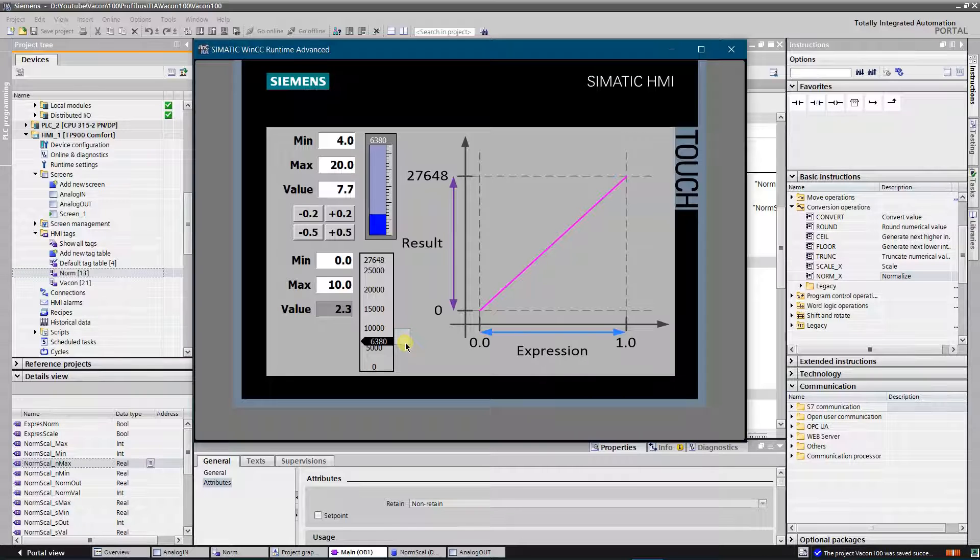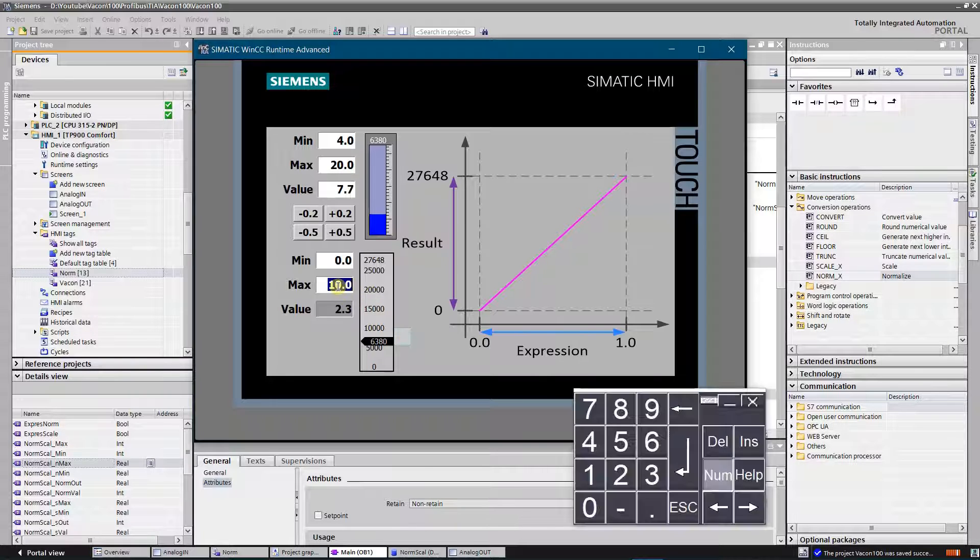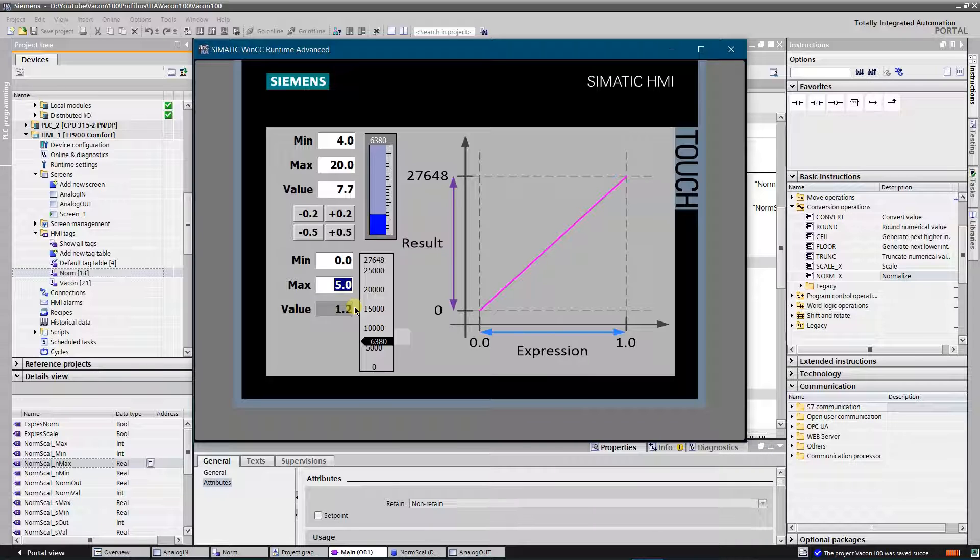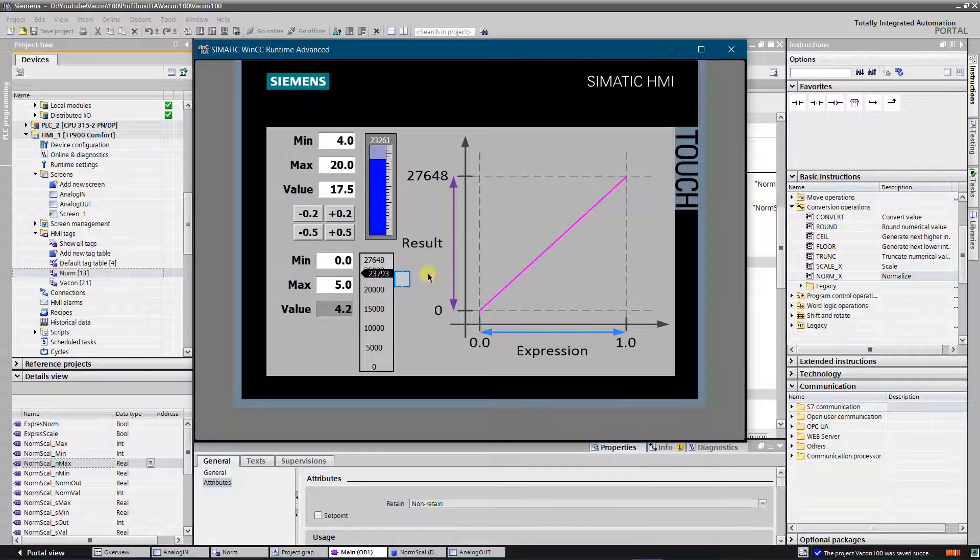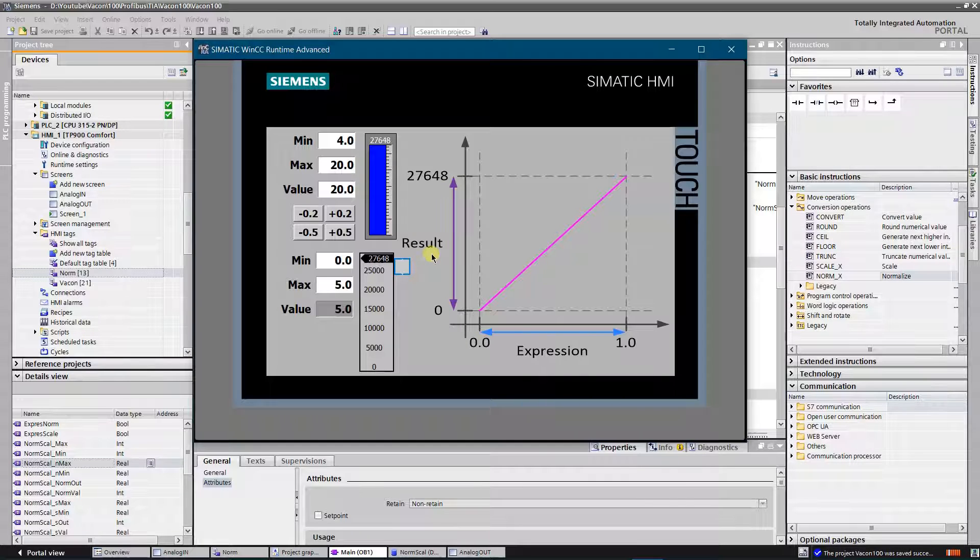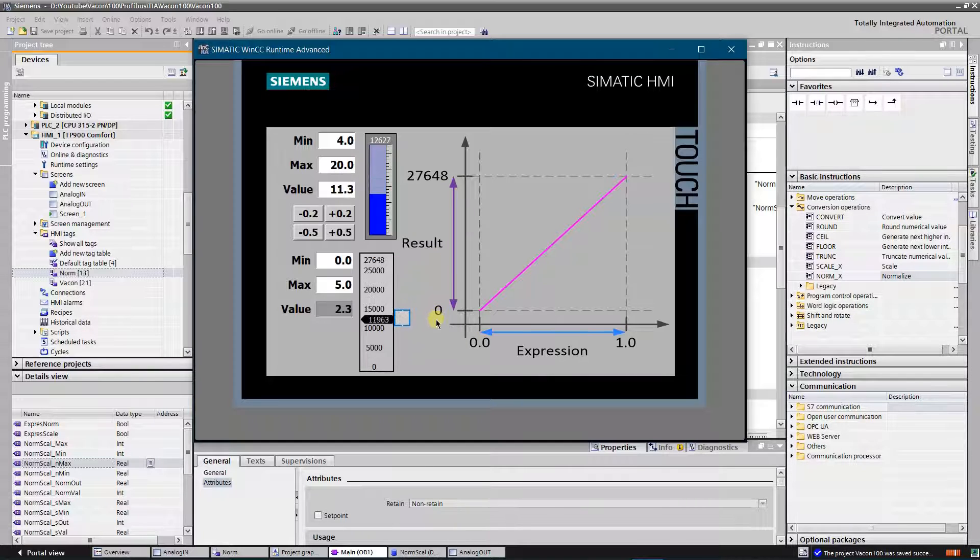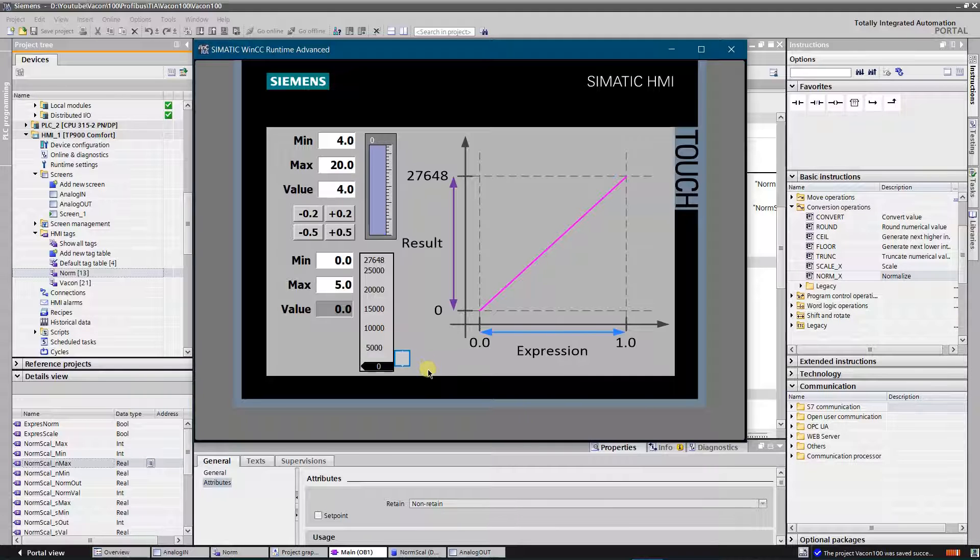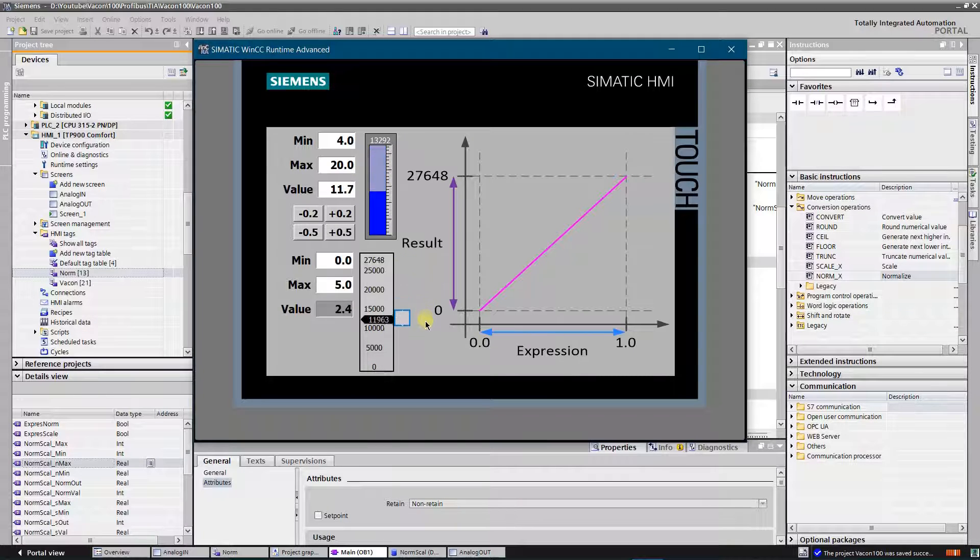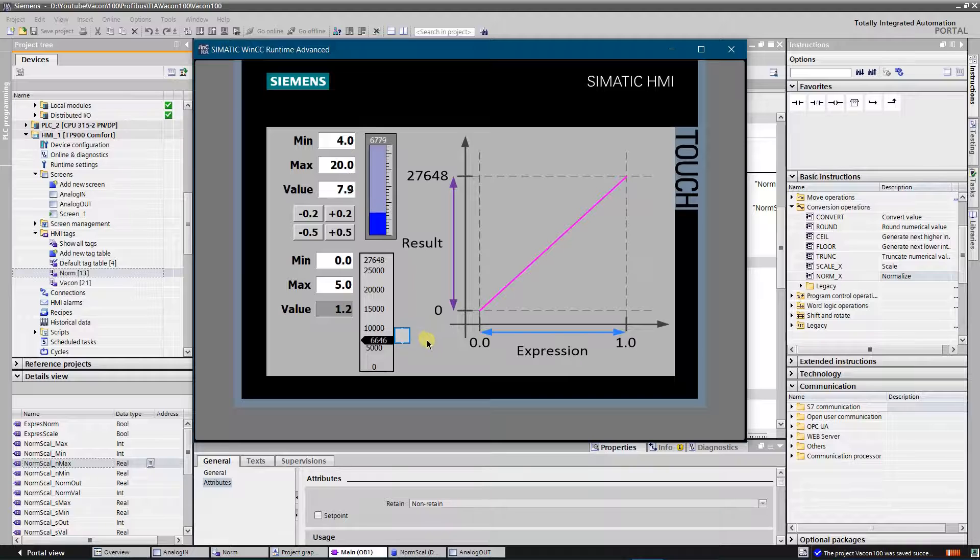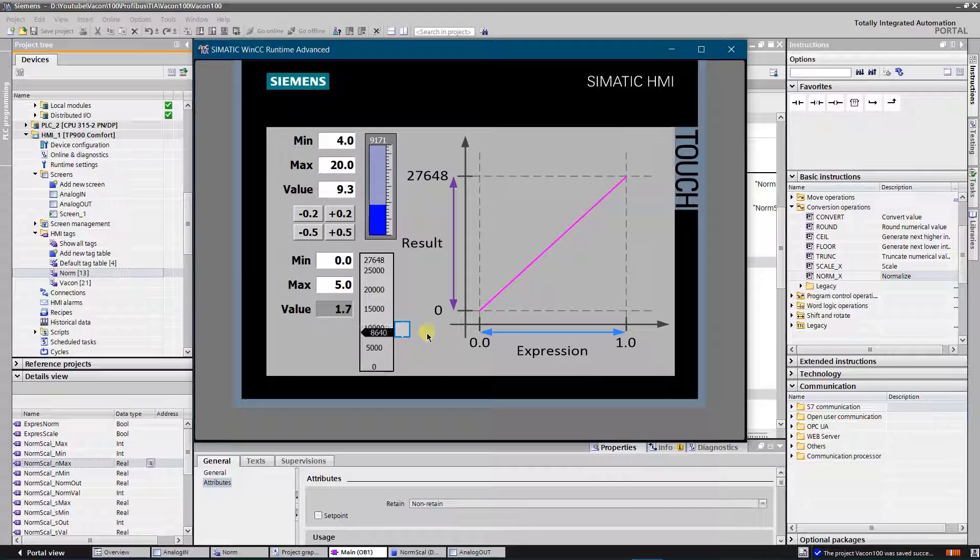I will try to change the limits of the analog input to the range of 0 to 5 volts. As you can see, the readings of the analog input varies between 0 and 5, while analog output setpoints varies between 4 and 20 milliamps.